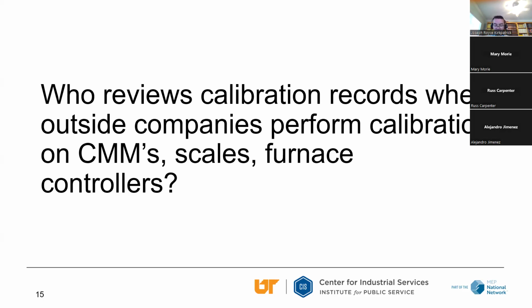One area where I see lots of findings in calibration related to external labs is if all the lab records or all the calibration records don't go through the lab, then there's a risk for failure there. And I do see that when, let's say, the purchasing group organizes and gets the calibration companies to come in, and they get the records and they keep the records, and they don't go into the calibration system or the laboratory. That's a recipe for disaster. I recommend all calibration records and reports go through the lab or go through your centralized calibration system.